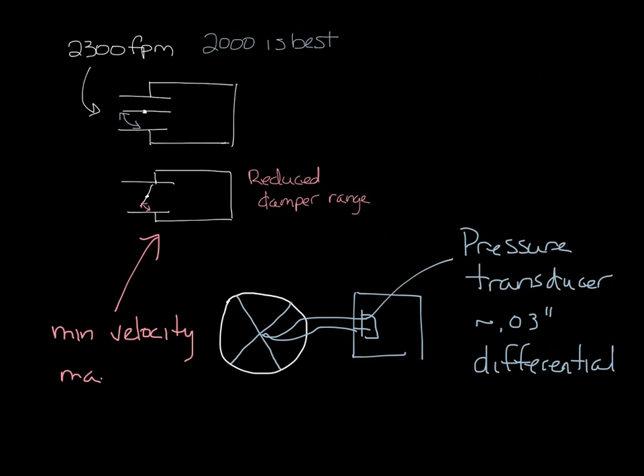And on that controller, you have a pressure transducer that is taking the pressure signal from your flow sensor. Most pressure transducers need about 0.03 inches of differential pressure from the flow sensor to control a box accurately. So in this case where your damper is oversized, your minimum velocity may result in a pressure reading from the flow sensor that is less than 0.03 inches. And then that means that your box will not be able to control as accurately at low flow.